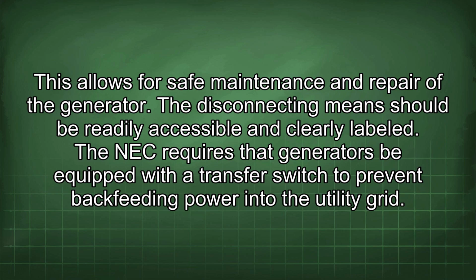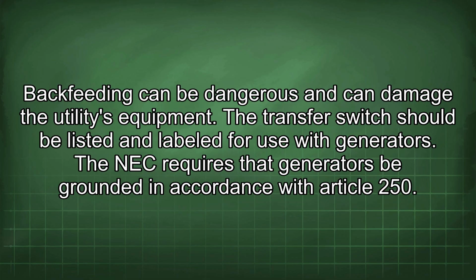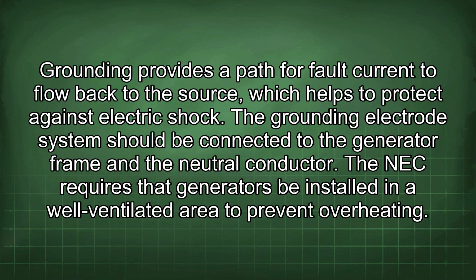The NEC requires that generators be equipped with a transfer switch to prevent backfeeding power into the utility grid. Backfeeding can be dangerous and can damage the utility's equipment. The transfer switch should be listed and labeled for use with generators. The NEC requires that generators be grounded in accordance with Article 250. Grounding provides a path for fault current to flow back to the source, which helps to protect against electric shock. The grounding electrode system should be connected to the generator frame and the neutral conductor.